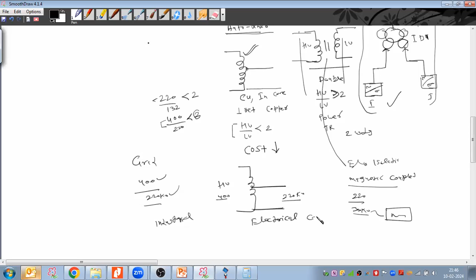Electrically connected. Am I correct on this? Electrically connected means my 400 kV substation and 220 kV substation are interconnected. So when my 400 kV substation is interconnected with the 220 kV substation, the transformer which I'm using is a single winding auto transformer. So the company will call this transformer either an auto transformer or an interconnecting transformer. Both are the same.